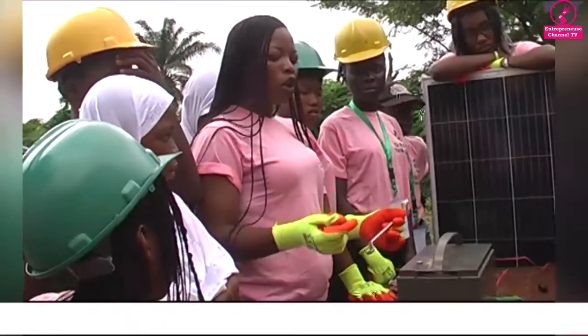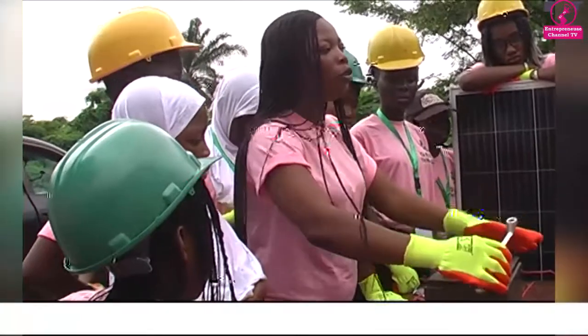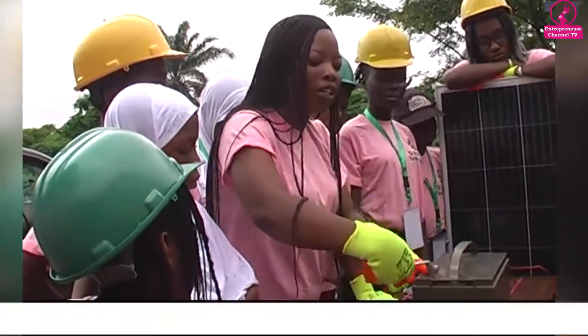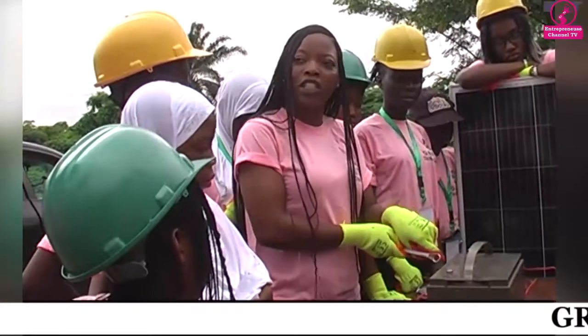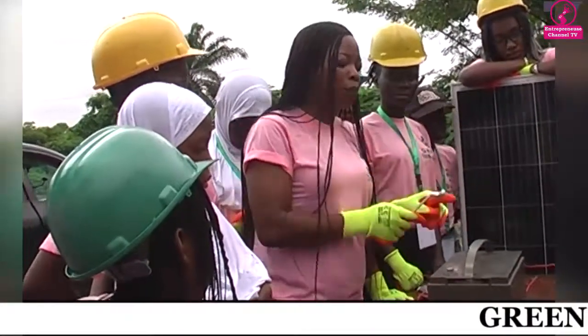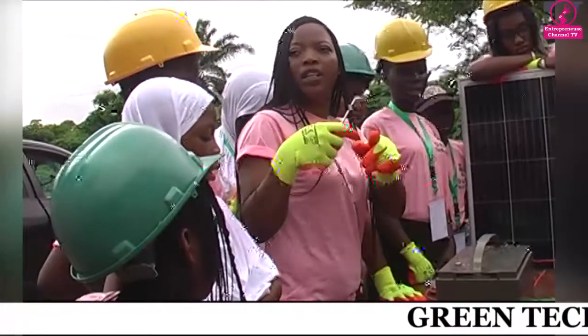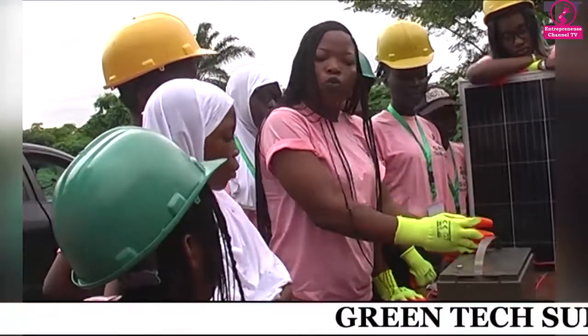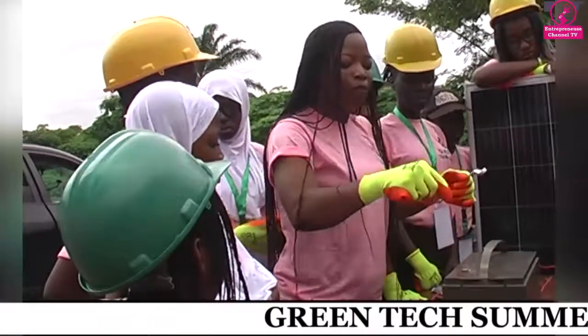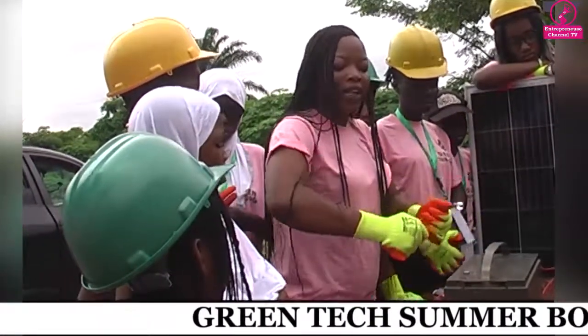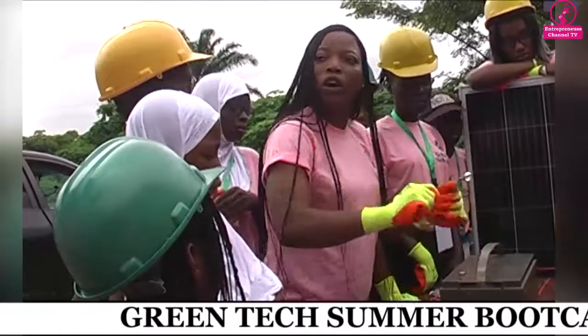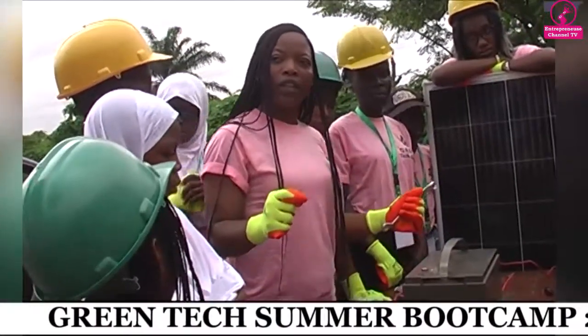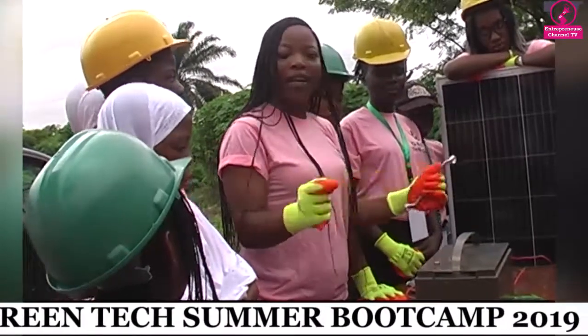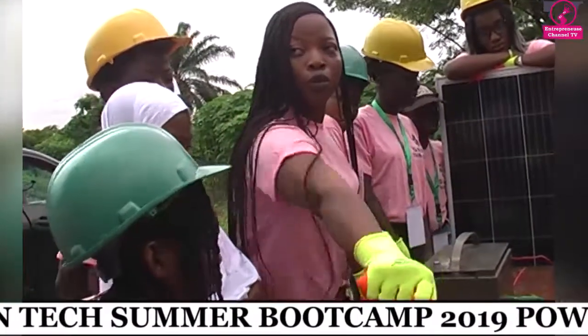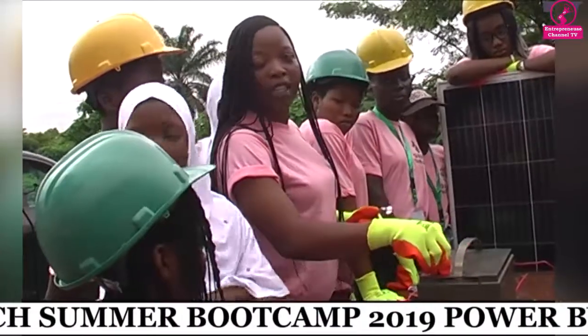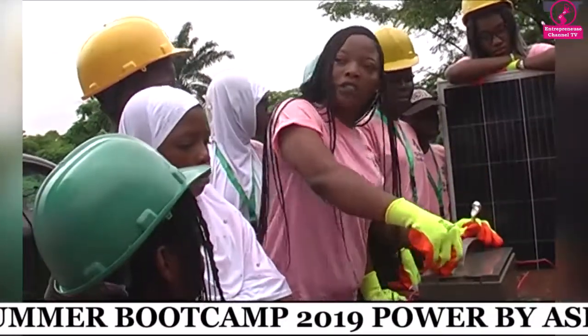So anytime you are working on batteries, when you are working on the negative side, run away from the positive side. And when you are working on the positive side, run away from the negative side. Concentrate on where you are working. And if you have put cables on them, separate them to a stage that they can never meet, so the negative side is separated from the positive side.